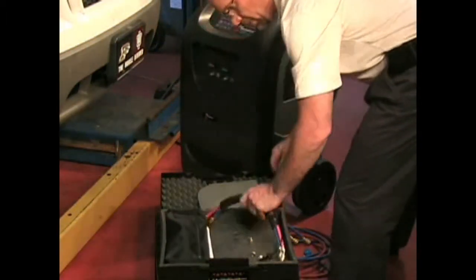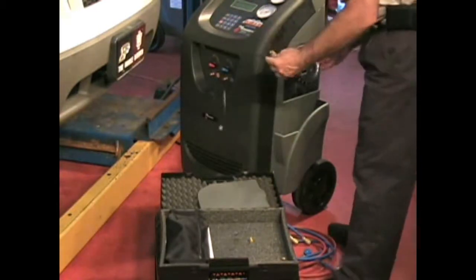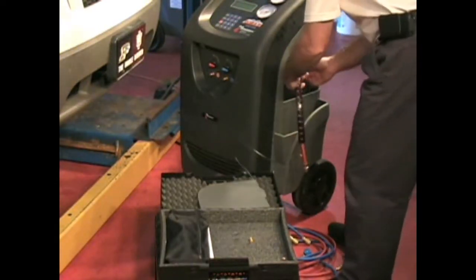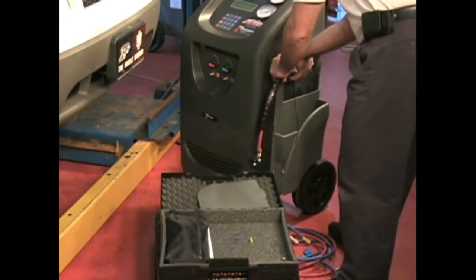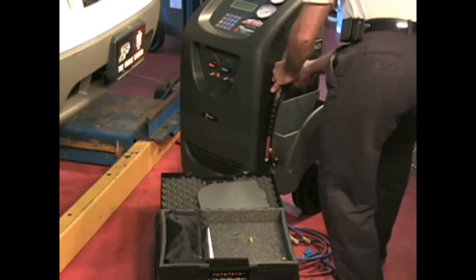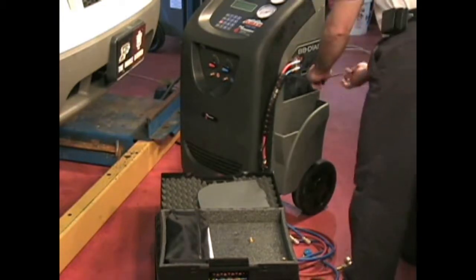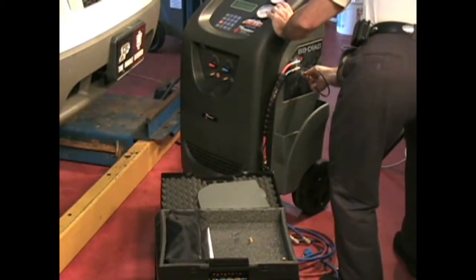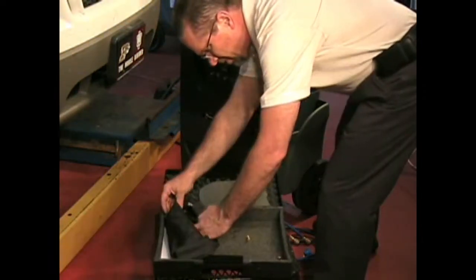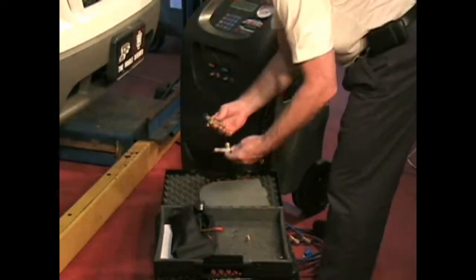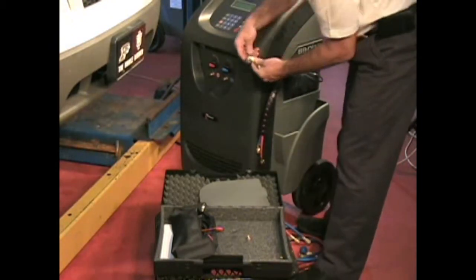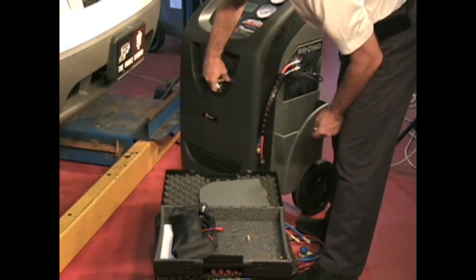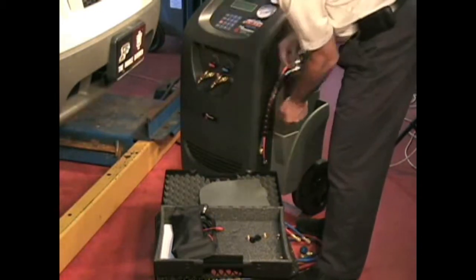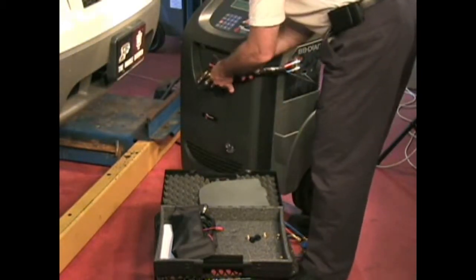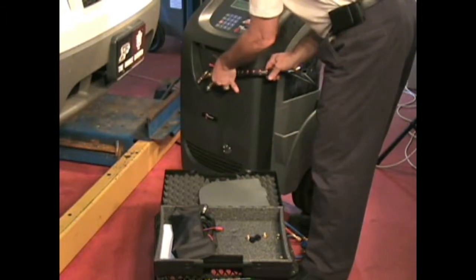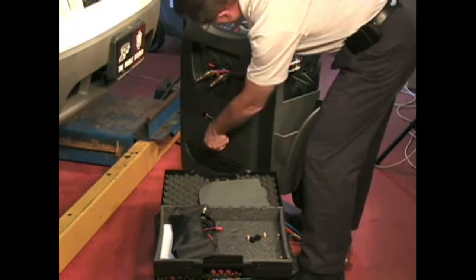Now remove the bag from the DM300 case and remove the hose and communications assembly and connect it to the DM300 ports. Blue hose to blue hose, red hose to red. Plug the modular communications cord into the DM300 port labeled COM. From the bag, remove the two-way hose adapters. Place one on both half-acme ports on the front of the CCST388. Connect the DM300 hoses to the smaller ports and the system hoses to the larger ports. Again, blue on blue, red on red.